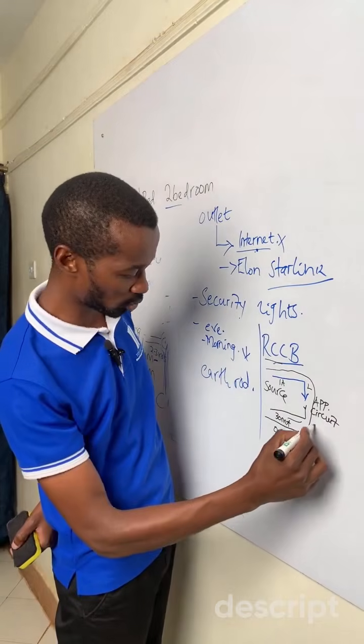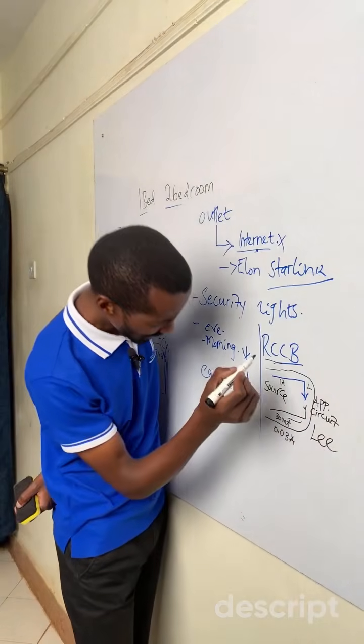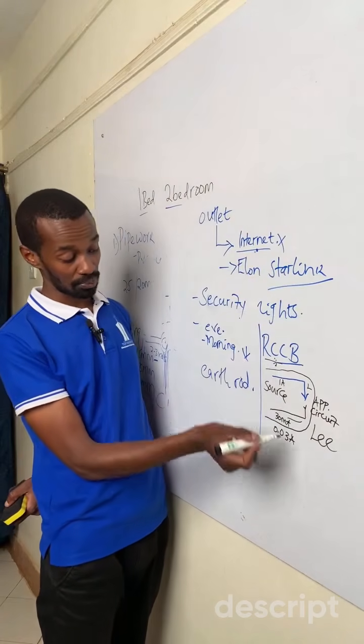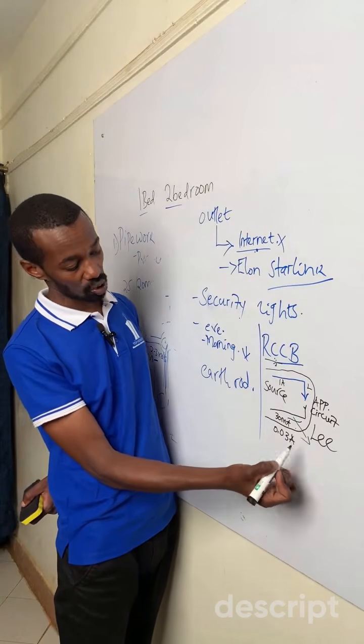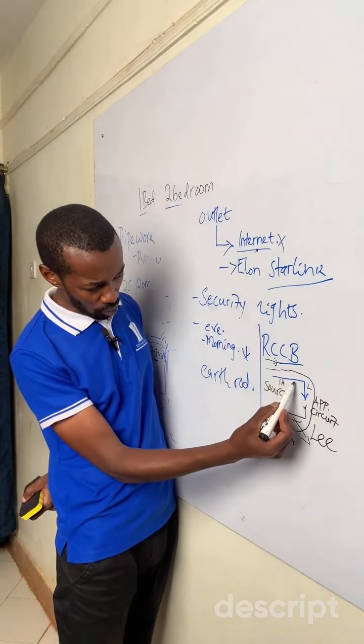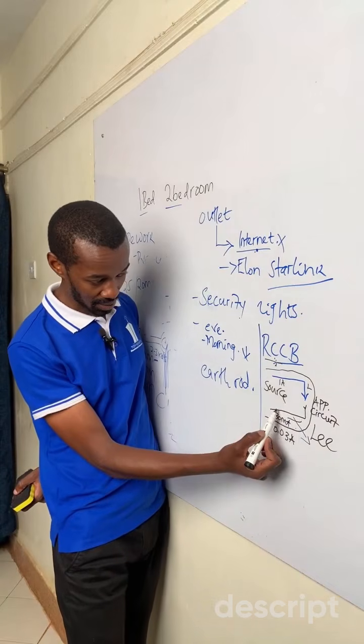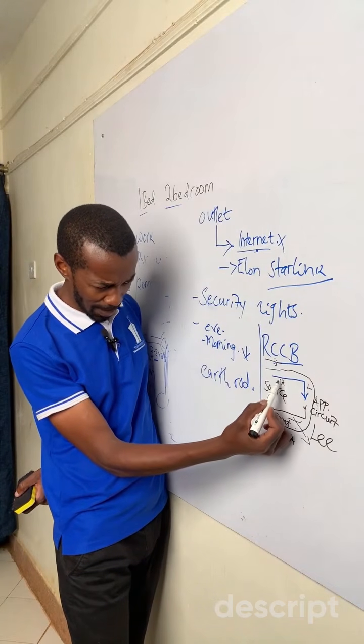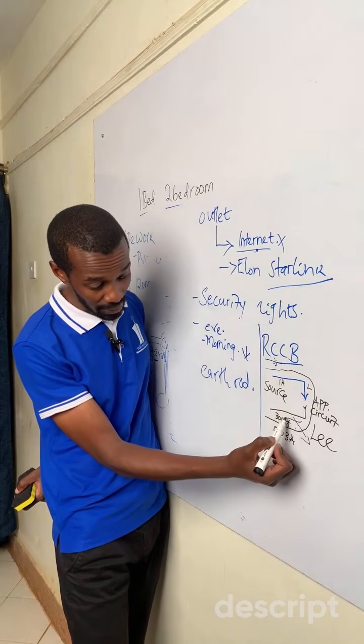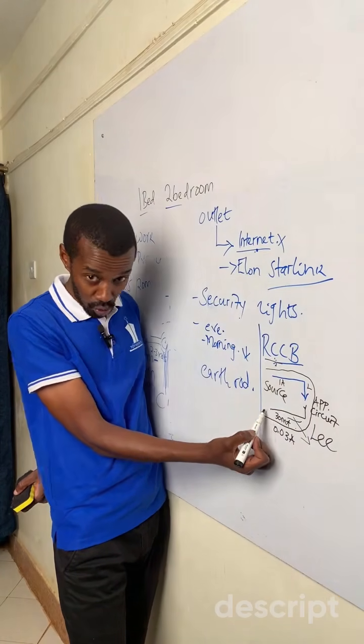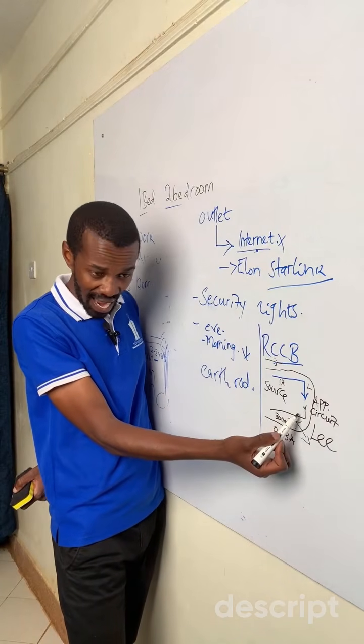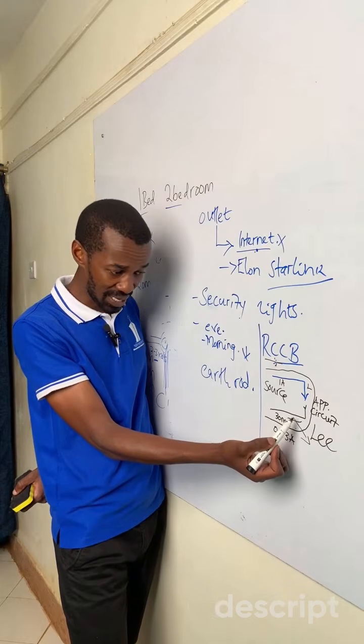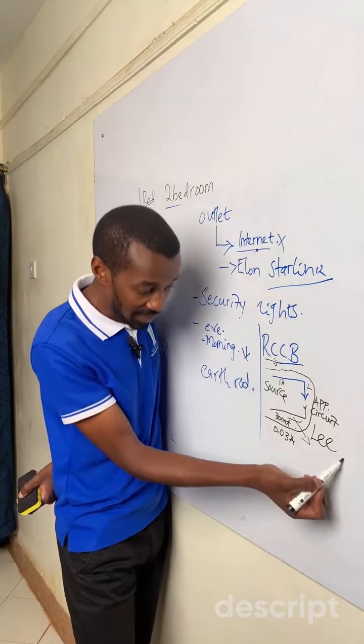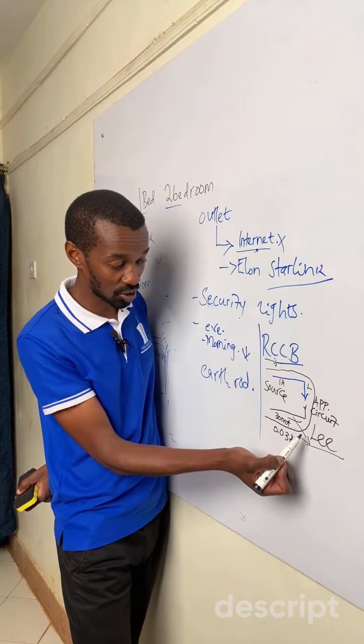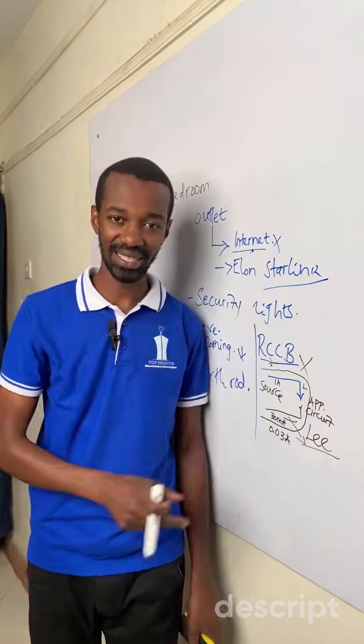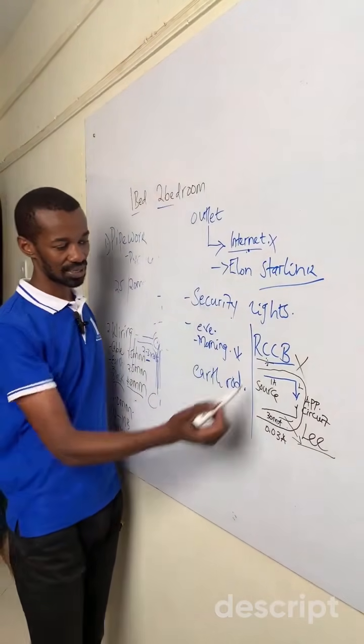So, assuming our top director Lee is receiving an electric shock, this RCCB is supposed to trip, because it has detected current leaving the circuit. It monitors whether the current flowing through the line — say 1 ampere or 1,000 milliamperes — is the same as the current flowing out of the circuit through the neutral. If there is only 970 milliamperes traveling back through the neutral, it will detect that Lee is being electrocuted at that point, and it will trip, shutting down the entire circuit so that we don't lose our brother. That is basically the operation of the RCCB.